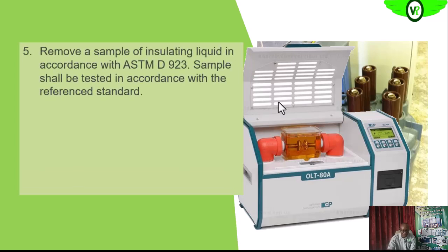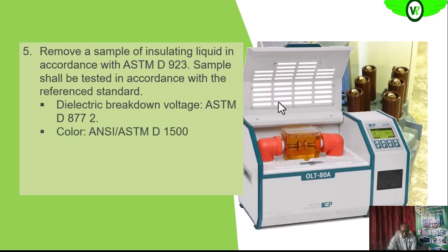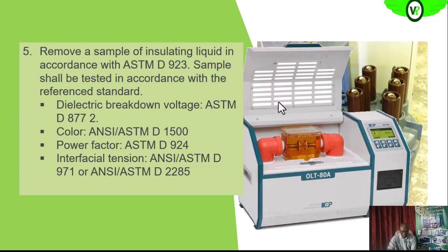Then the oil too, we want to take a sample of the oil and then test the sample of the oil. We'll test for the dielectric strength of the oil, that is the breakdown voltage of the oil, in accordance to ASTM D877. So that is what we want to do. We also want to look at the color. So the color should be as bright as possible, as recommended by the ANSI or ASTM D1500 standard. Okay. Then we also want to test the power factor that has to do with the insulation too of the oil. So we test that. Then the interfacial tension, we also want to look at that.